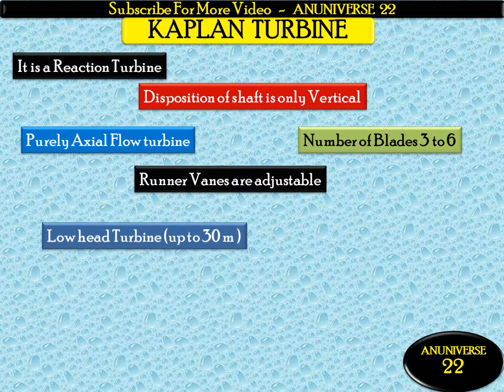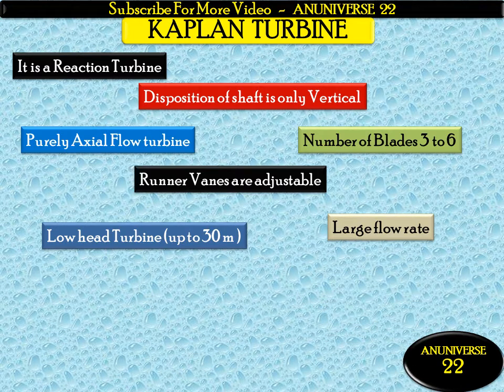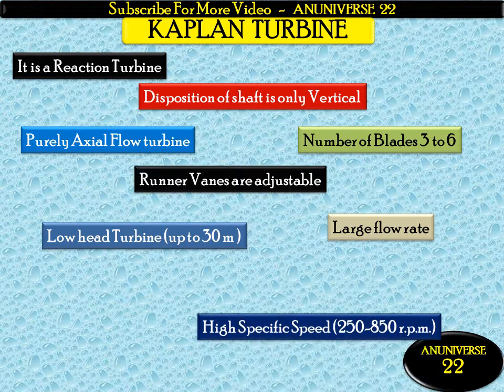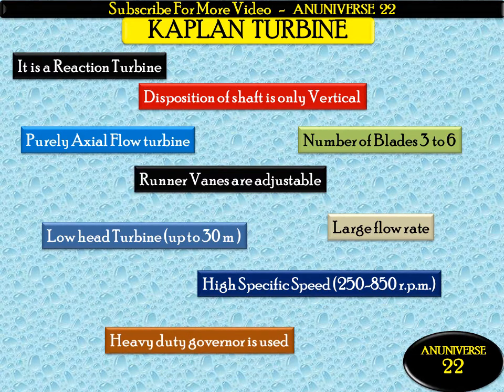It is a low head turbine, up to 30 meters, with a large flow rate, low head, and high discharge. It is a high specific speed turbine, and the speed varies from 250 to 850 RPM. A heavy duty governor is used for governing of this turbine.